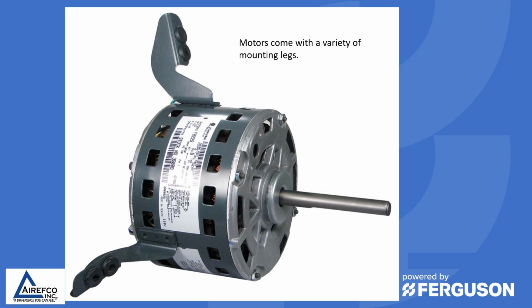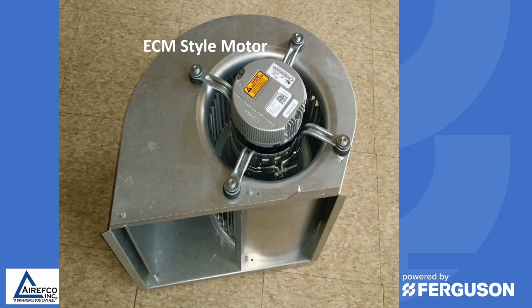As we said, most of your modern furnaces now have ECM style motors with the electronics on the back end of them. And for proper troubleshooting of these motors, you need to have the manufacturer's troubleshooting guides to know the proper voltages. One of the most common calls that we get in tech support is from a tech who says he has the high voltage to the ECM motor, but it's not running. And they have a misconception that just because it has high voltage, the motor should be running.